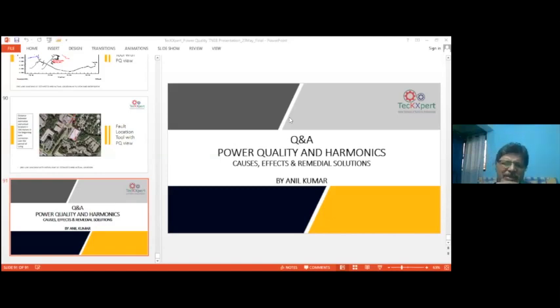But if the harmonic current distortion is very small, then you cannot use this harmonic power flow basis, because the power flow will be very little, so you will not be able to easily identify it. Again, harmonics is something which happens in the time domain. With a single load connected to a grid, it's very easy to say which direction the harmonics is flowing. If you have multiple loads, all the loads are not working in the same sequence. So it's a very difficult exercise, even though some of the manufacturers say we can do this.